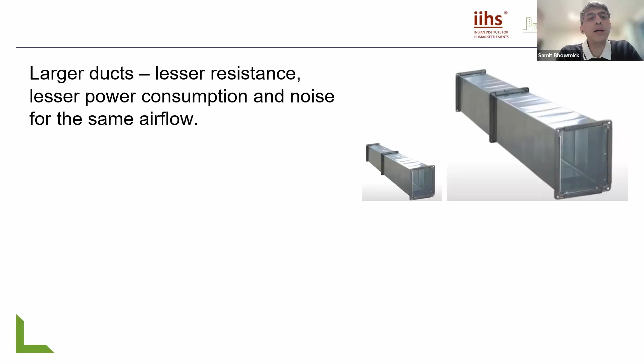This is because of this formula. I know this is a common sense strategy, but this is a very simple formula, and it's important to at least remember the relation. The pressure drop in a duct or a pipe is inversely proportional to the fifth power of the diameter, which means that if I reduce the duct diameter by half, the power consumption increases to 32 times. Half, and 2 to the power 5 is 32. So this is a significant impact, and we underestimate this in our daily practices.